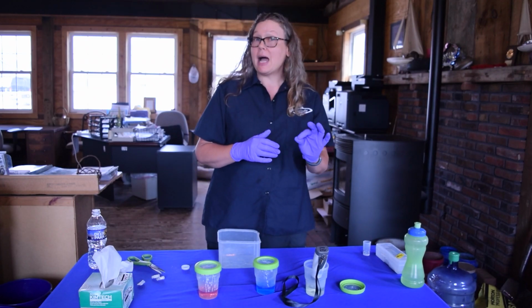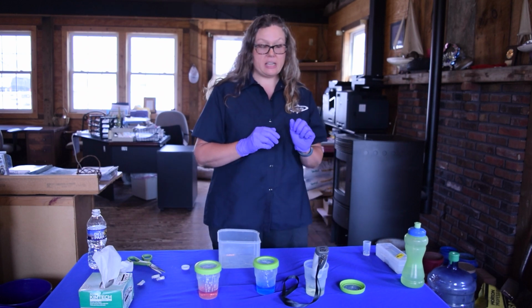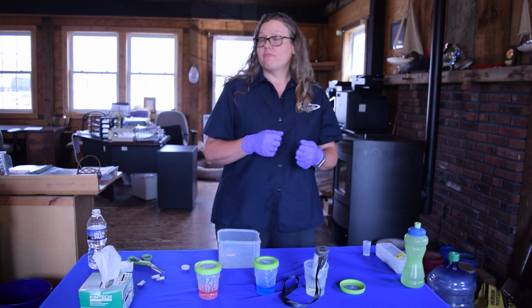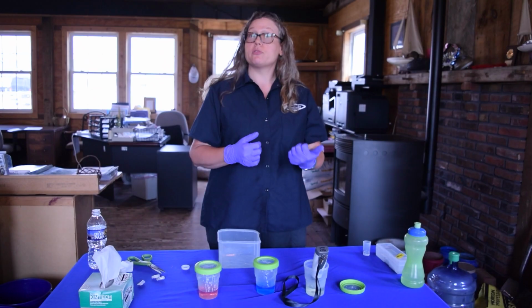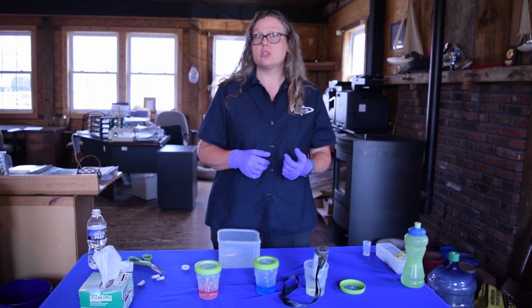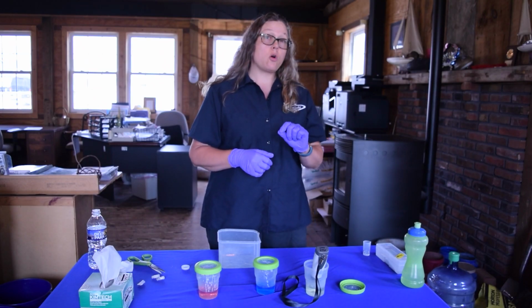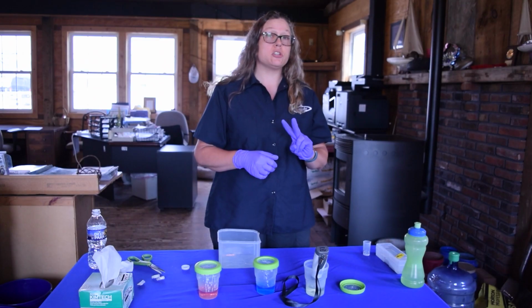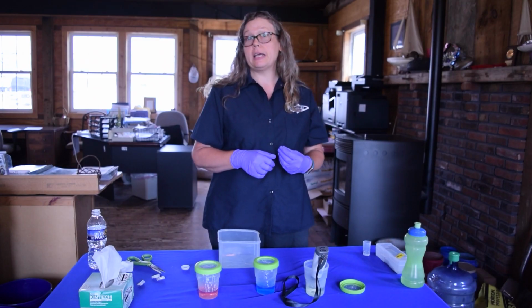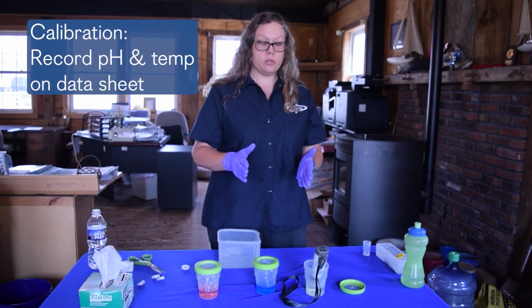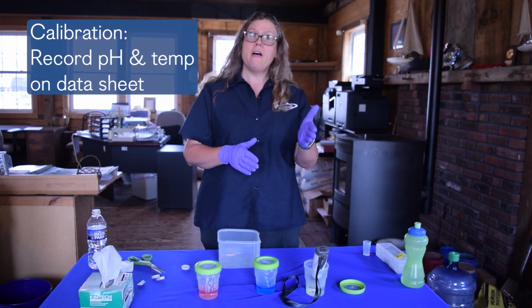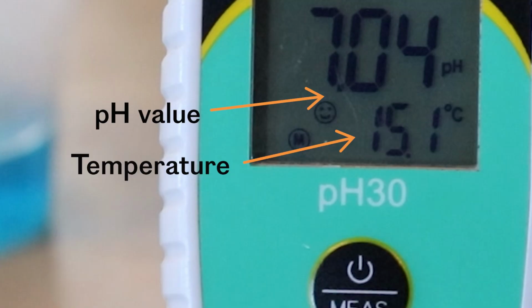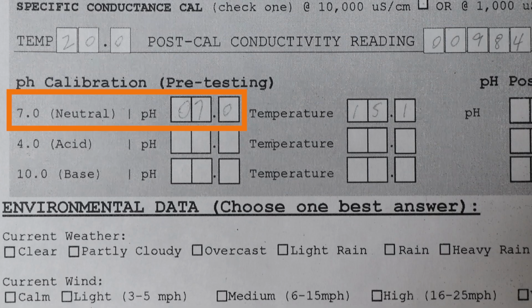When you see a smiley face and the smiley face has stayed that way for 5 to 10 seconds, you can proceed with the calibration process. You'll want to make sure that you record 2 things on your data sheet. On the site sample data sheet in the calibration section, you want to record the pH value that is shown on your screen, and you'll want to record the water temperature as well.